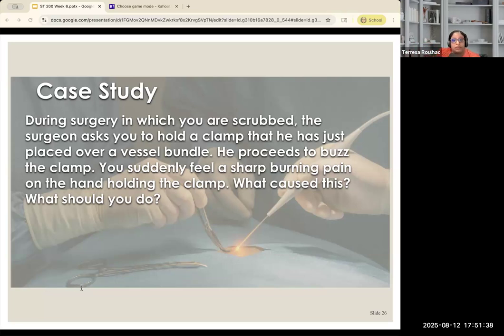Some causes: improper grounding or insulation. Monopolar cautery requires a grounding pad, so if it isn't placed correctly or there's an insulation issue, it may not be fully attached to the skin. The current escapes through the nearest conductive path trying to find that grounding pad, and if it can't, it goes for the metal clamp you happen to be holding. So the clamp is metallic, keep that in mind. It provides a direct path for the electricity, and your hand is what feels it, which isn't ideal.